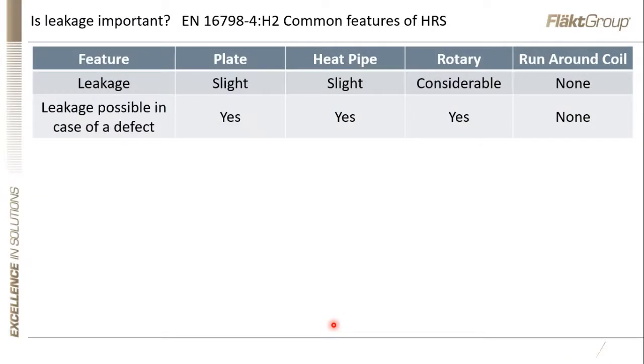So is that leakage important? There is reference to it in EN 16798-4, common features of heat recovery systems. It says that leakage from plates and heat pipes is slight. From rotaries can be considerable. Runaround coils, obviously, with separated airstream, there is no leakage. But what is the leakage possible in the case of a defect in the heat recovery device? It could be large in the respect of plates, heat pipes, and rotary heat exchangers. Of course, runaround coils, separate airstreams.